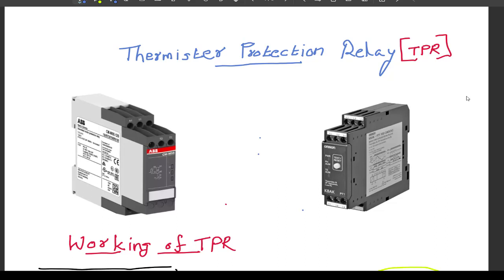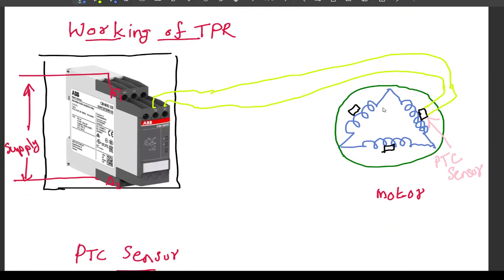The thermistors are PTC sensors, like temperature sensors. They are incorporated in the windings like this. This is a three-phase delta winding of the motor, and these are the sensors. These sensors will sense the temperature of the winding during running, and if it is more, it will give feedback to the relay. If the temperature exceeds a certain limit value, the relay will cut off the supply so that the motor will trip. Normally you cannot find it in small motors.